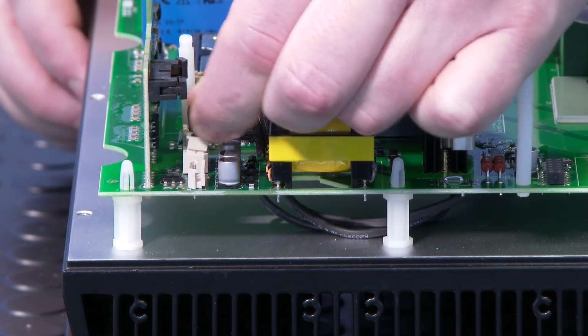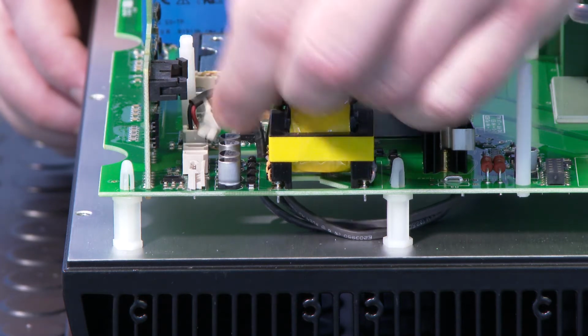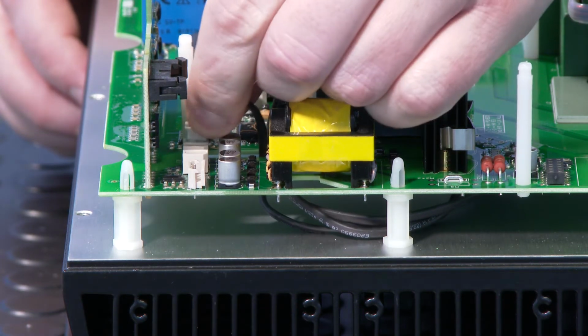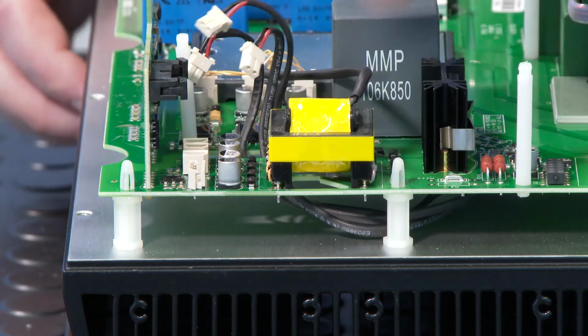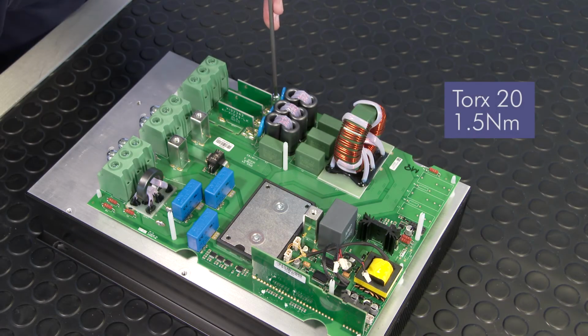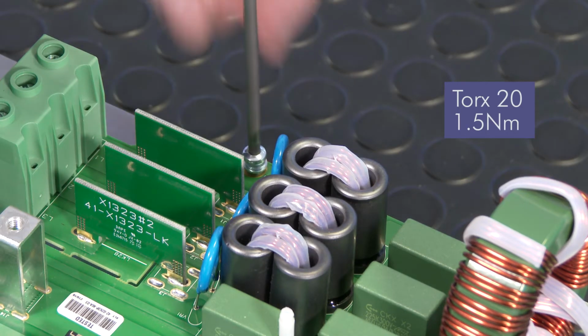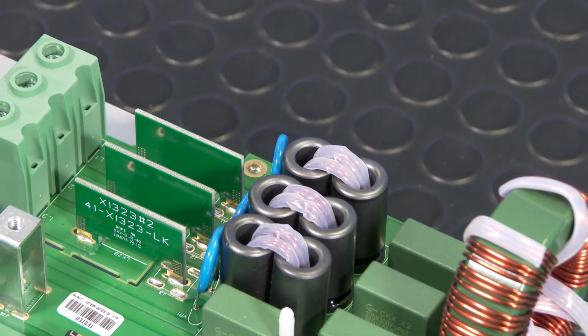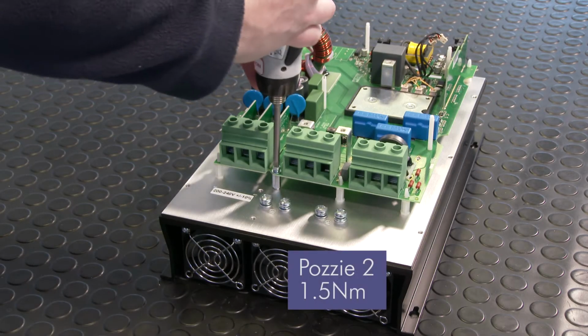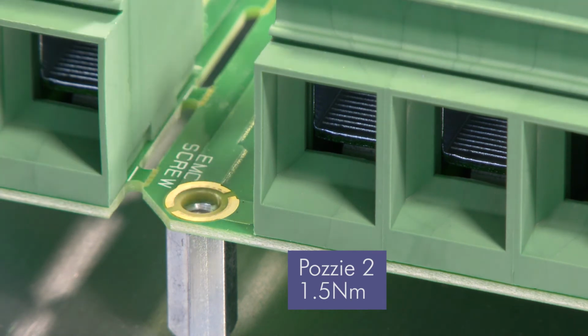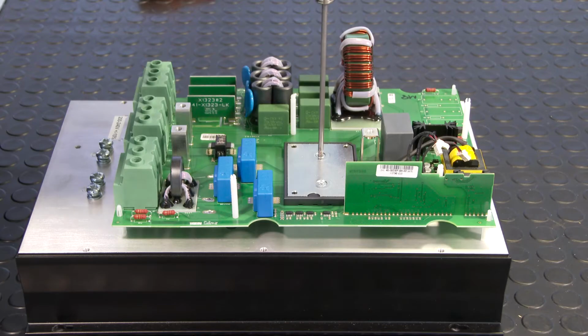Remove the heatsink cooling fans by pulling the cables away from the connectors. Use a Torx 20 screwdriver to remove the earth screw. The torque setting is 1.5 Nm. Use a POSI 2 screwdriver to remove the EMC screw. The torque setting is 1.5 Nm.